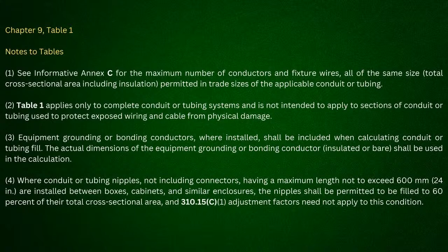It's not from end to end. So if I go back here and look at note 2, it says that it has to be a complete conduit or tubing system. Well, how can it be complete if I don't complete it on one end? Yeah. So if you go look at the informational note here, this ties it in even more, and it specifically tells you, by NFPA Enhanced Content, that that is considered a sleeve, and that is to protect those cables from what? Physical damage. Yeah, so one of the situations that I brought up to you was, let's say you have 10 cables coming out of the underground, direct bury, and you just sleeve them through a PVC into the panel. Why would you need to adjust? I don't get that. It's a short section. It's not complete on both ends. All it's doing is protecting from emergence from grade, which is required.